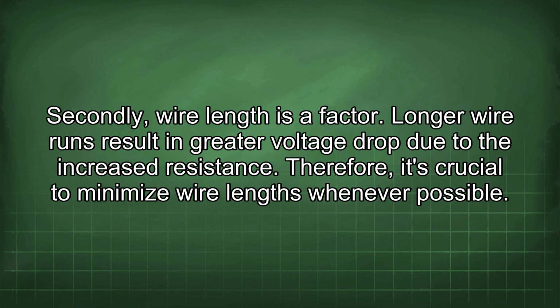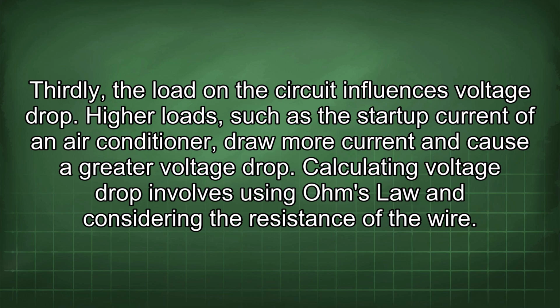Secondly, wire length is a factor. Longer wire runs result in greater voltage drop due to the increased resistance. Therefore, it's crucial to minimize wire lengths whenever possible. Thirdly, the load on the circuit influences voltage drop. High loads, such as the startup current of an air conditioner, draw more current and cause a greater voltage drop.